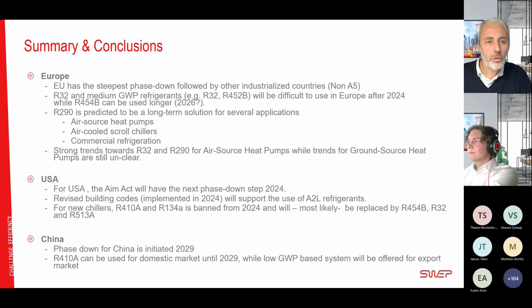All right, to conclude this webinar, starting with Europe, EU has the steepest phase down, followed by other industrialized countries defined as non-A5. We see that R32 and medium GWP refrigerants, typically R32, will be difficult to use in Europe after 2024 when we have the next phase down. But we see that 454B can be used a little bit longer since it has a GWP of 466. It's actually below the average GWP of 2024.